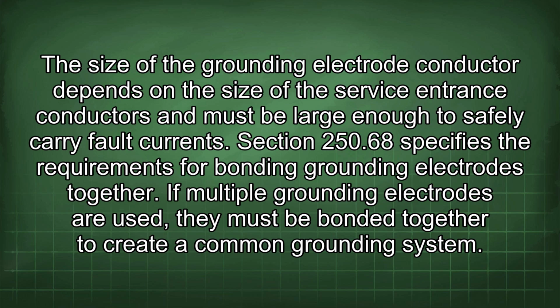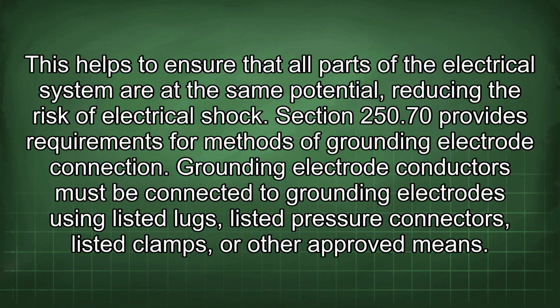Section 250.68 specifies the requirements for bonding grounding electrodes together. If multiple grounding electrodes are used, they must be bonded together to create a common grounding system. This helps to ensure that all parts of the electrical system are at the same potential, reducing the risk of electrical shock.